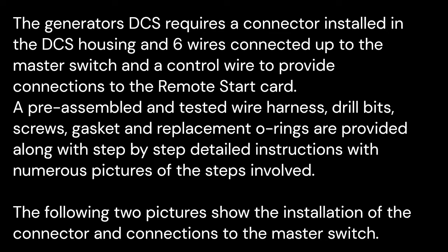The generator's DCS needs a connector installed in the housing and the connector's leads connected up to the master start switch, as well as a control lead to provide connection to the remote start card. A pre-assembled cable harness, drill bits, screws, gasket, and O-rings, as well as detailed step-by-step instructions with numerous pictures of all the steps is provided. The following 2 pictures show the installed connector and the connections to the master start switch.